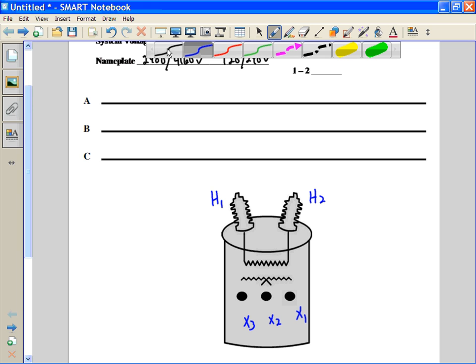And let's connect the secondary coils inside the transformer. In this case, we need use of the full length of the coils tied together, so we're going to connect them in series. In other words, just connect them end to end to make one long coil, and show the connections coming down to the bushings themselves. And we utilize all 3 bushings on the secondary side.